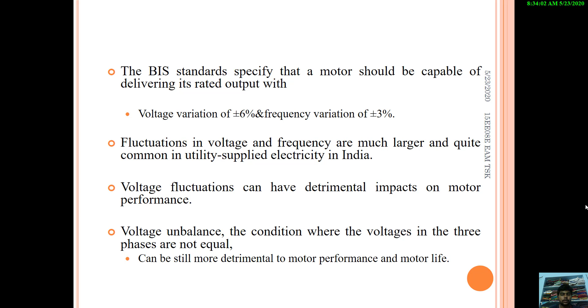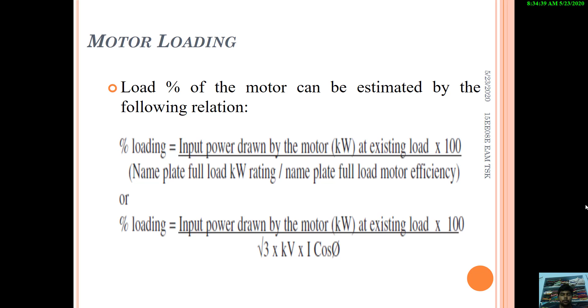The next one is motor loading. Loading is the percentage loading, which can be calculated as the input power drawn by the motor in kilowatts at the existing load, divided by root 3 into kV into I cos phi, that is VI cos phi, into 100 in order to make it a percentage. Or it can otherwise be calculated as the input power drawn by the motor in kilowatts at the existing load divided by the nameplate full load kilowatt rating, or nameplate full load motor efficiency.